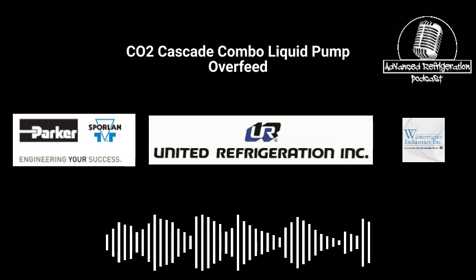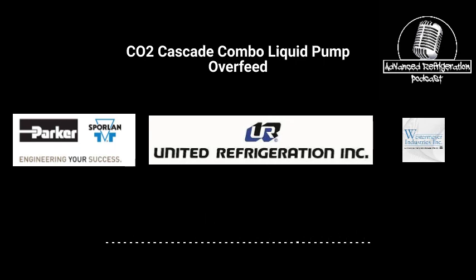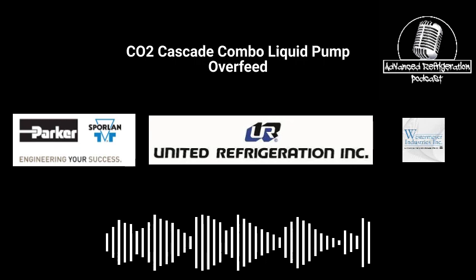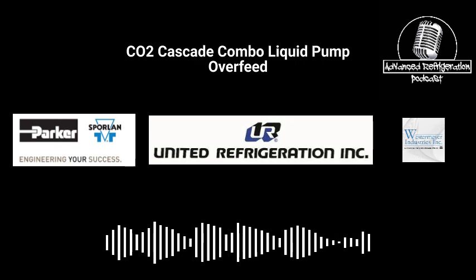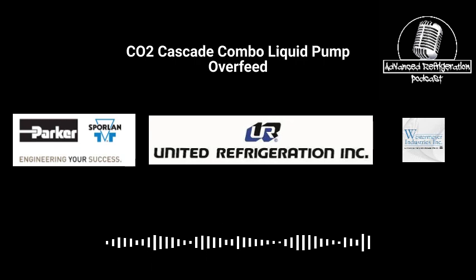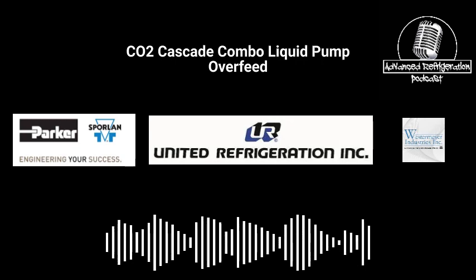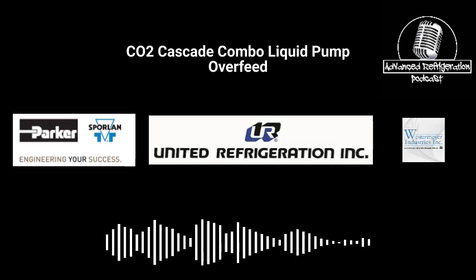So on this particular rack, we're going to run probably about a 17-degree midpoint, so about 43 pounds if you're dealing with 449 or 448. And then the heat exchanger's set point for the superheat is typically about 6 to 10, is what I've seen. Some people put it up a little bit higher, especially if they're having loading issues.